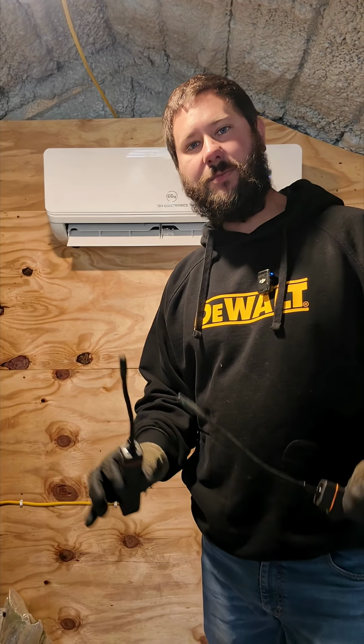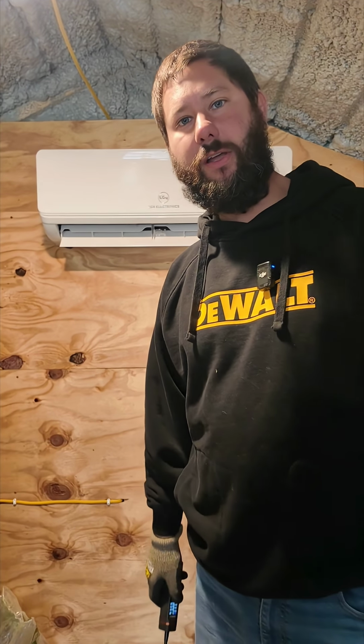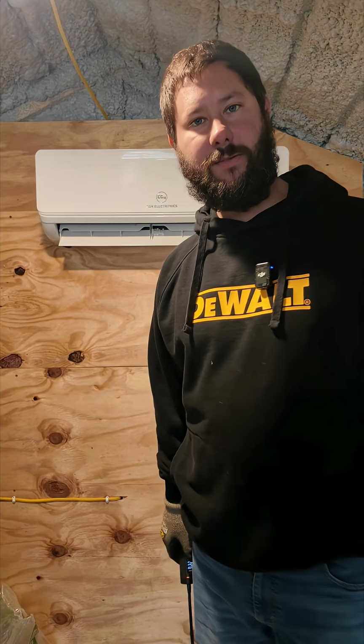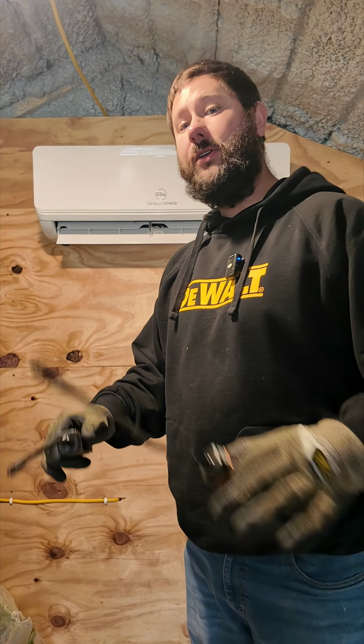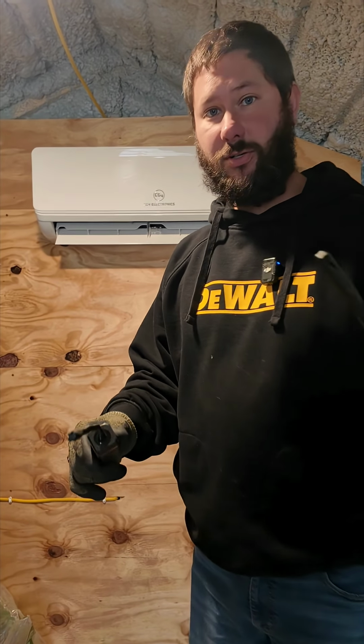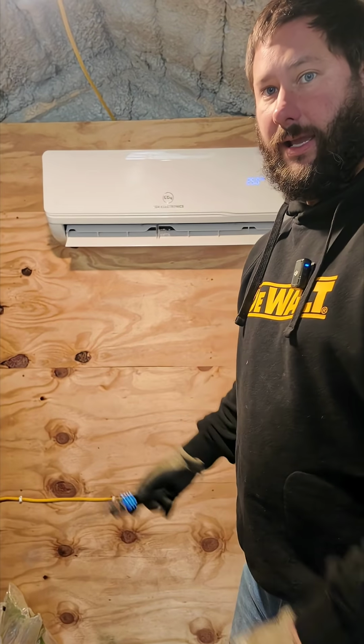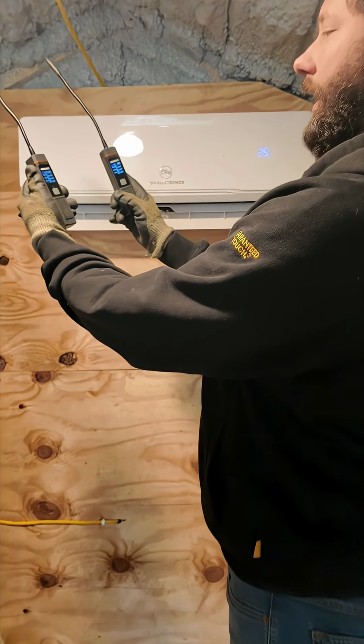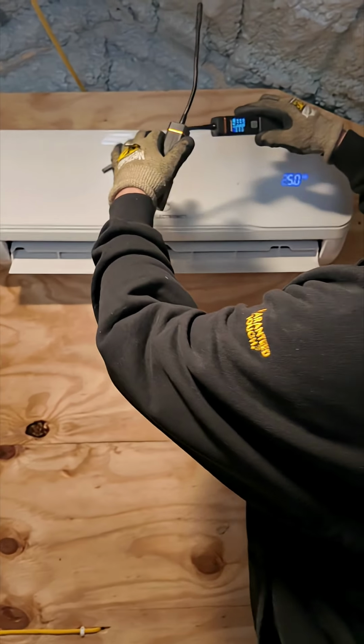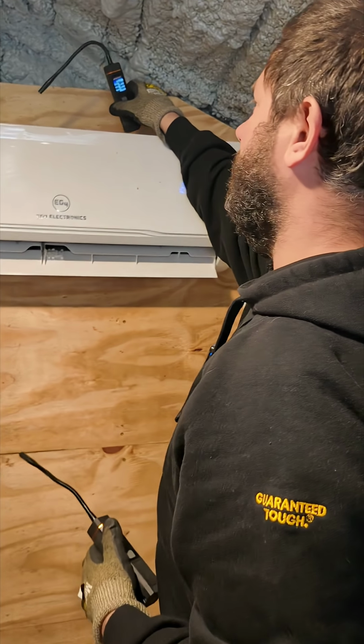How do you know if your mini split is heating properly? Today I'm going to show you how to check temperature split on a mini split in the heat mode, and I'm going to show you the pressures and temperatures of our lines on the outdoor unit. So first, we got two probes. You can use one if you want.